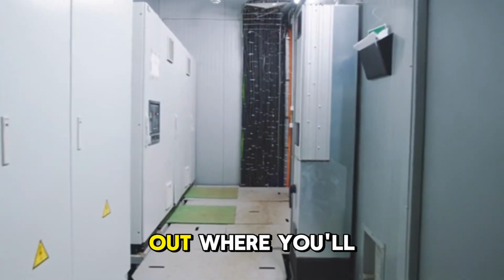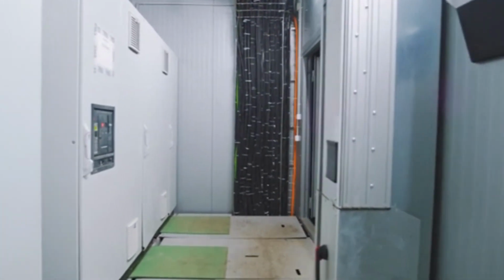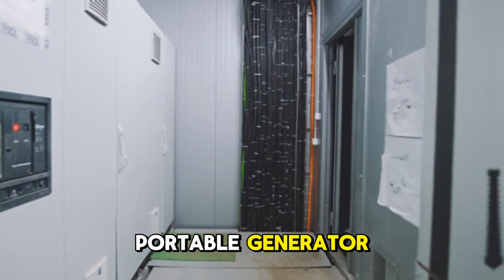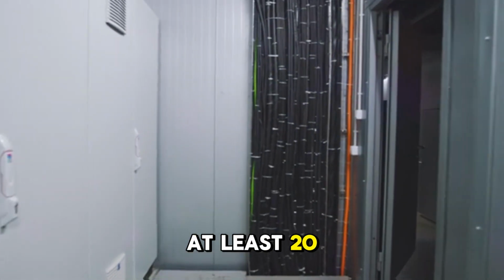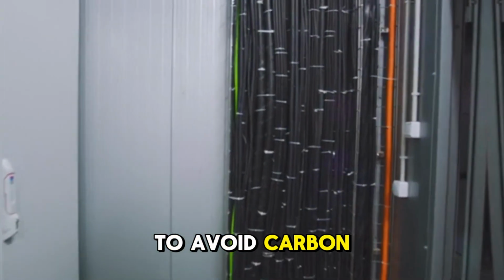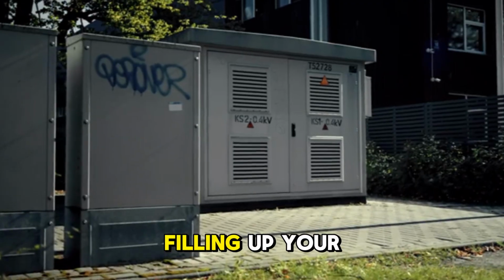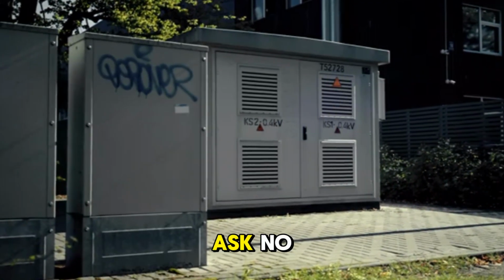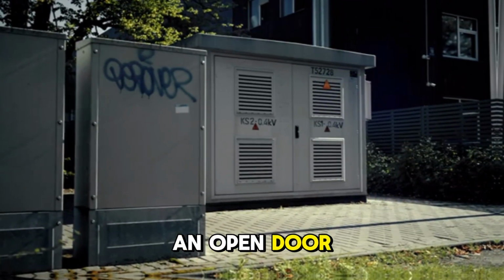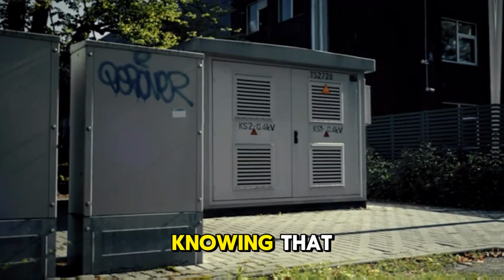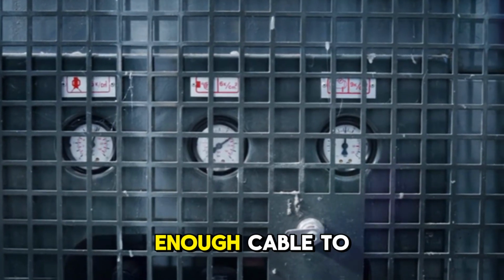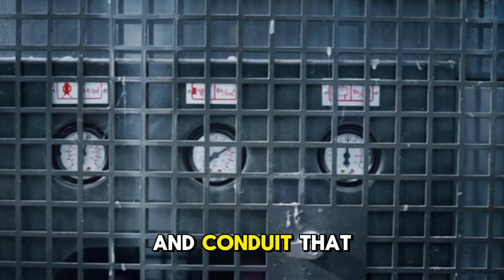Also, you should plan out where you'll set up your generator. If you're using a fuel-based portable generator, you must position it at least 20 feet or so from the house to avoid carbon monoxide from the generator's exhaust filling up your home. Before you ask, no, a garage with an open door is not safe. Knowing that, make sure you have a long enough cable to reach a wall outlet and conduit that can connect to the transfer switch.